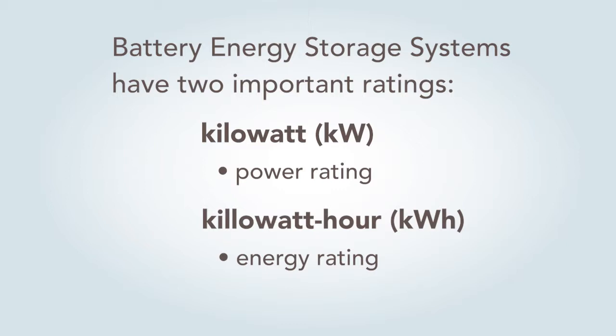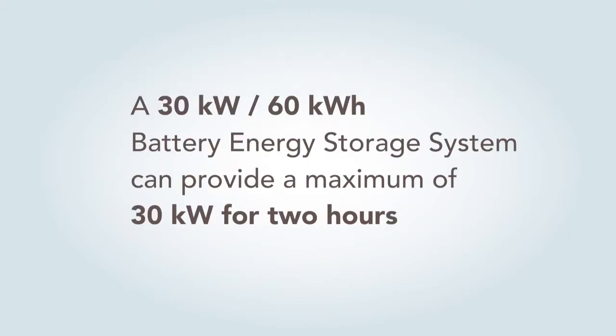Really, you have power and you have energy. If it's a 30 kilowatt system and it's discharging at 30 kilowatts, it's going to last for 2 hours because it's 60 kilowatt hours. Now, it is variable. You can discharge at 10 kilowatts, discharge at 15 kilowatts, but say you're discharging at 15 kilowatts. Well, if it's a 60 kilowatt hour system, you get 4 hours operating at that level. Some of the utility scale systems will usually be 4, 8, even 12-hour systems. But if you're installing a commercial or even a residential system, they're usually 2-hour systems. That's kind of the standard we see.